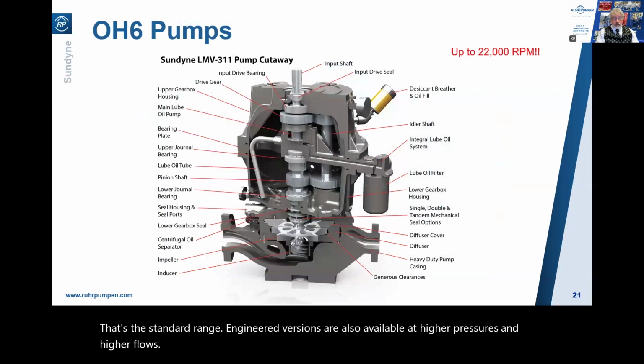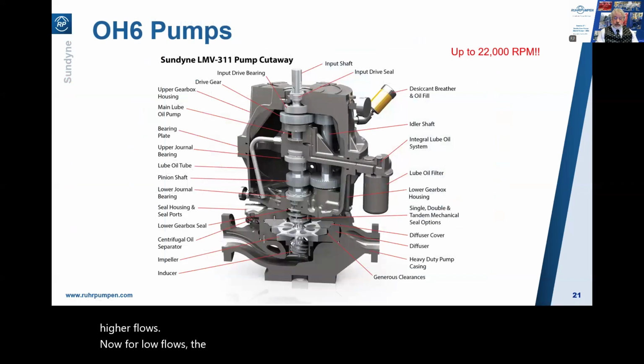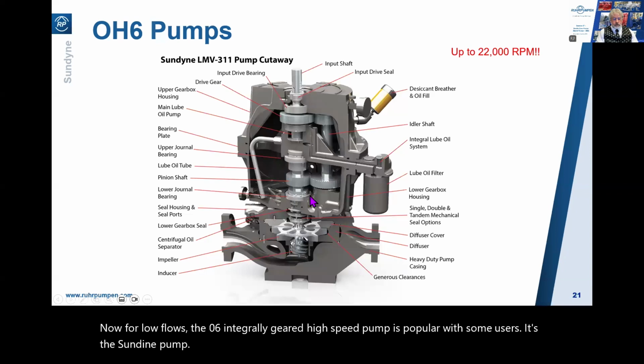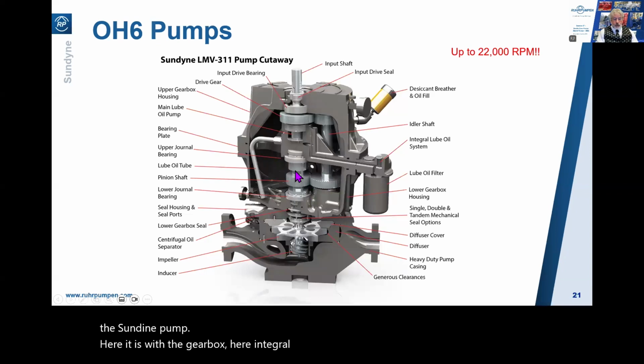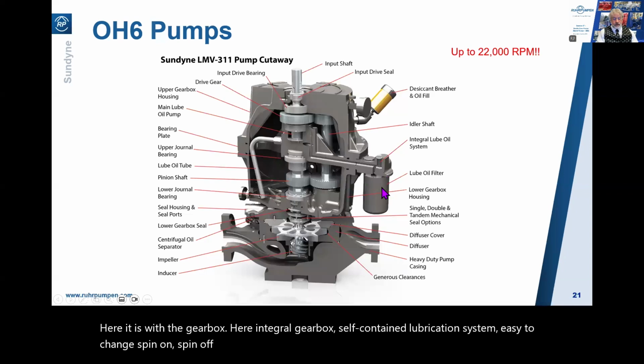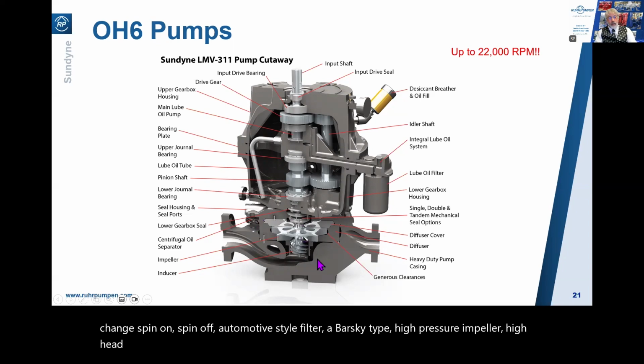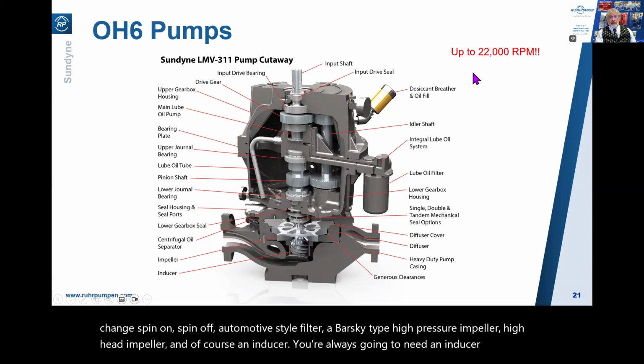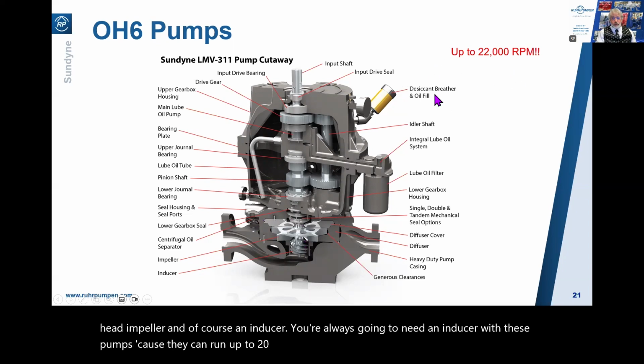Now for low flows, the OH6 integrally geared high-speed pump is popular with some users. It's the Sundyne pump. Here it is with the integral gearbox, self-contained lubrication system, easy to change spin-on, spin-off automotive-style filter, a Barske-type high-pressure, high-head impeller, and of course an inducer. You're always going to need an inducer with these pumps because they can run up to 22,000 RPM. So you can imagine what that does to the NPSH required.